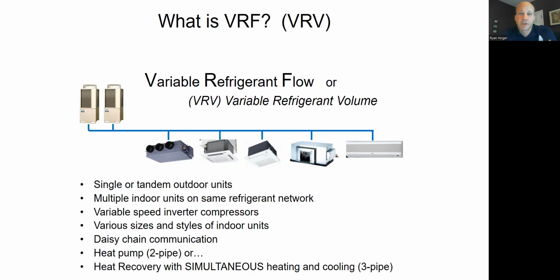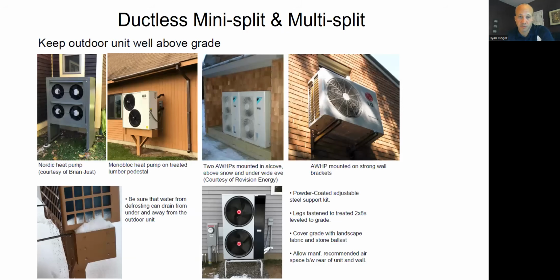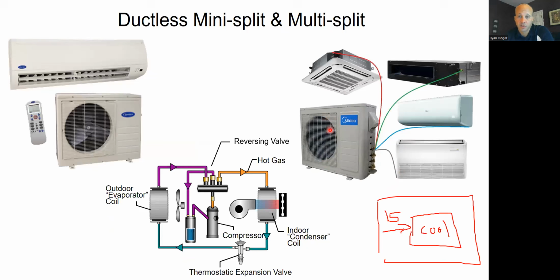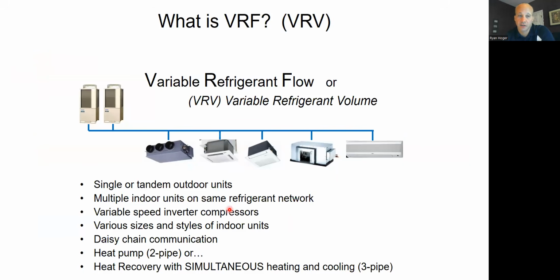So VRF stands for variable refrigerant flow. One manufacturer calls it VRV, variable refrigerant volume, but everybody else calls it variable refrigerant flow. So generically, VRF is what you hear stated. This is very similar to that mini split we were talking about, a multi-zone mini split, right? It was similar to this scenario where I have multiple indoor units on a single outdoor unit. Same kind of idea here.